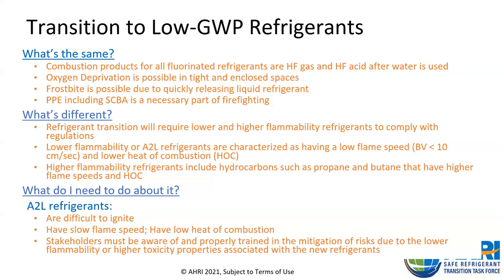What's different? The refrigerant transition will require lower and higher flammability refrigerants to comply with these regulations, right? The AIM Act will require that. And lower flammability refrigerants, or A2L refrigerants, are characterized as those refrigerants having a low flame speed or burning velocity less than 10 centimeters per second and lower heat of combustion.